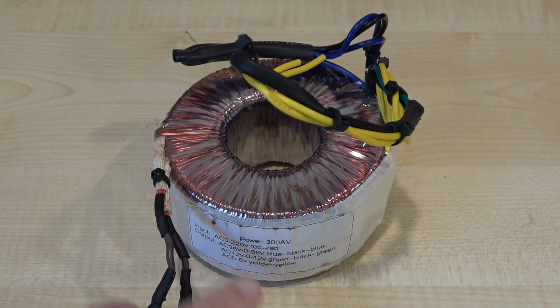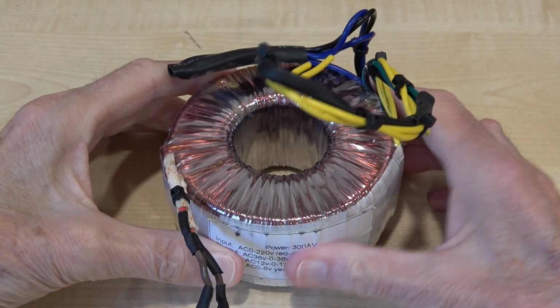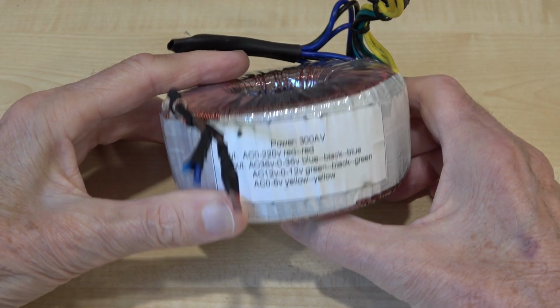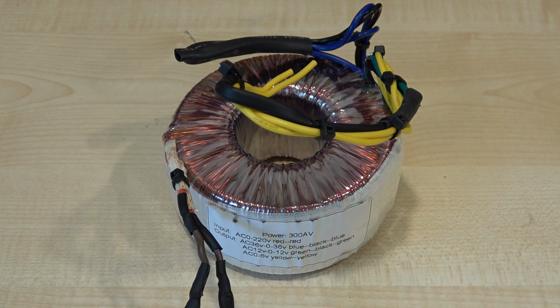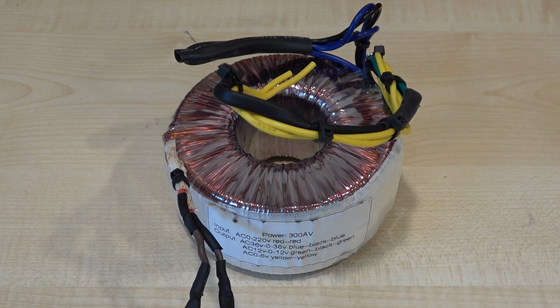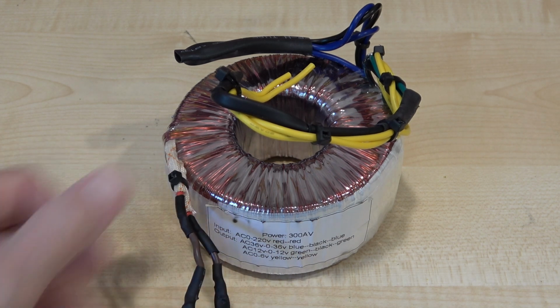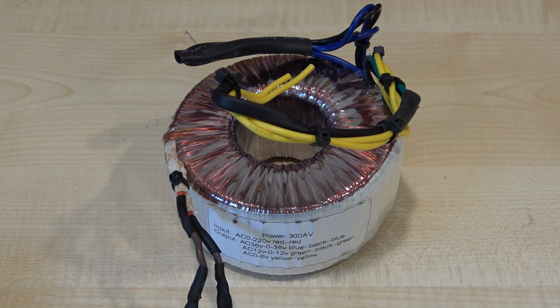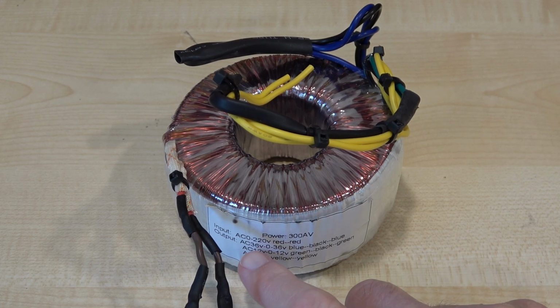Now in the case of New Zealand, whether you can see this or not, let's lift it up a little bit. This says 220 volts. Now that is because if you buy these from China directly, that is what they would call a universal voltage, and what it really means is it isn't suitable for any country. Here in New Zealand we typically have 240 volts as the nominal voltage, as indeed I believe so does Australia and certainly the UK. This transformer you can use with a 220 volt primary.